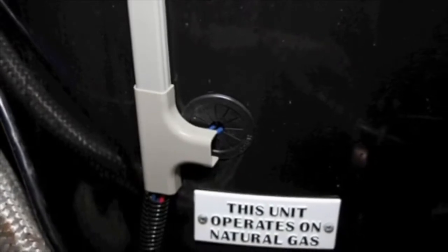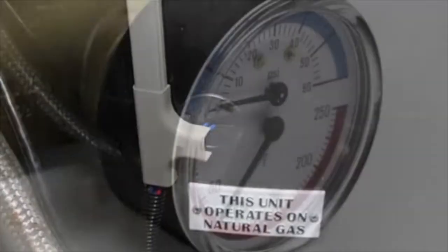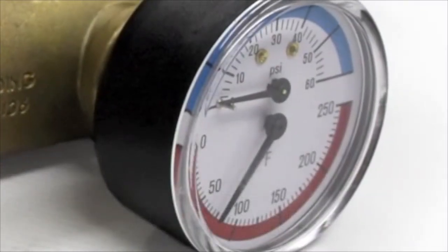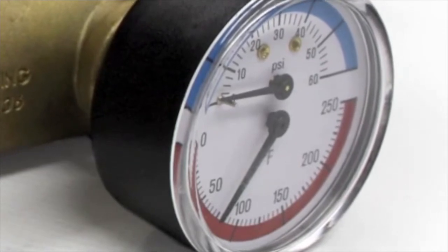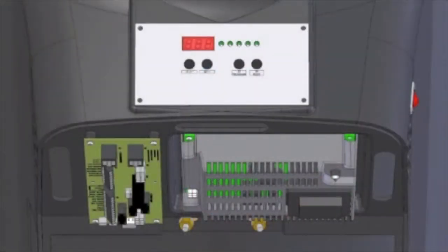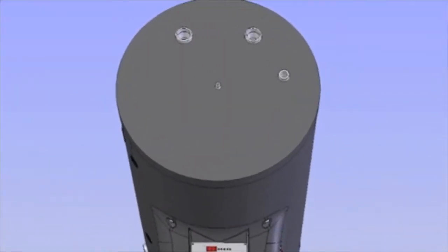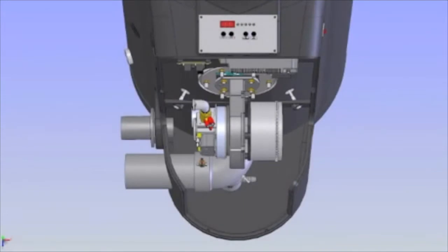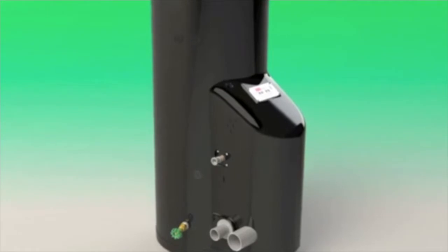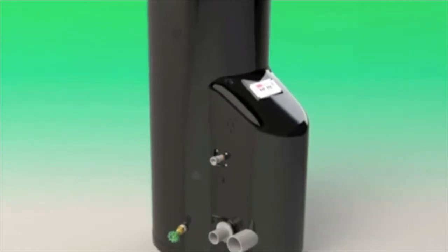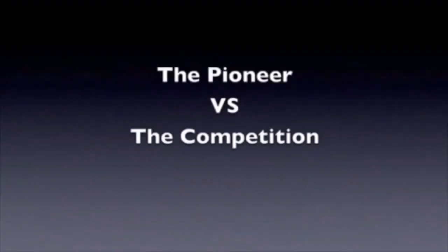The temperature and pressure gauge allows the user to monitor system temperature and pressure. The integrated control system monitors return and supply water temperature and regulates the unit's BTU output by controlling fan speed, allowing the unit to deliver only the amount of heat and energy required.